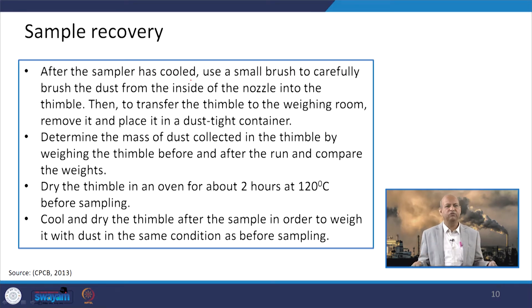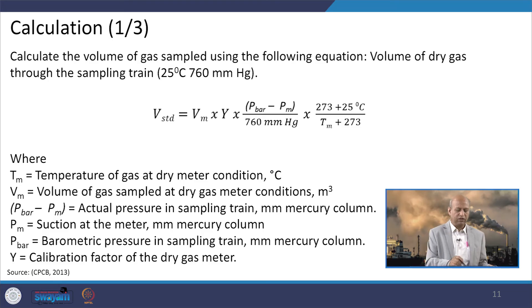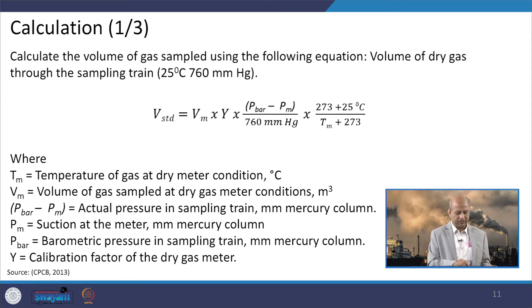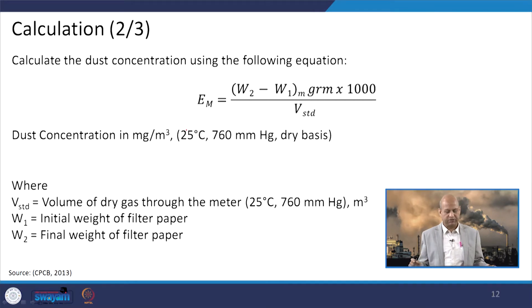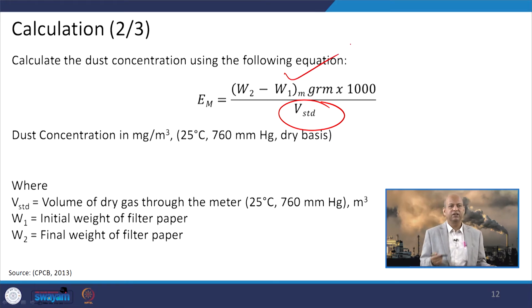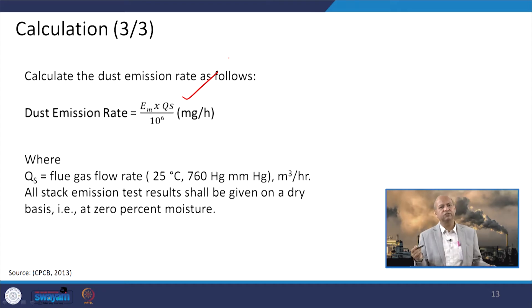To calculate the volume of gas sampled, we use a relationship involving pressure difference, volume of gas sampled at dry gas meter conditions, and temperature corrections. This gives the volume of gas sampled. That value is used to divide the weight difference, yielding the concentration — weight divided by the volume. To calculate the dust emission rate, we multiply the concentration by the flow rate Q_s, which gives the emission rate. This way we know both the concentration and the emission rate.